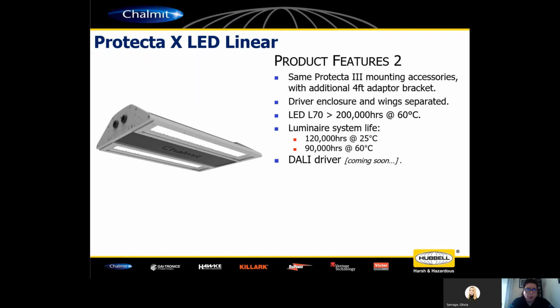I'm sure you're all aware that LEDs and electronics on the whole do not like high temperatures. They also don't like extreme low temperatures, so there's definitely a balancing act required there. Essentially, the point to take away is that at a sustained ambient of 60 degrees, the Protecta X luminaire will still achieve round about 10 years before you need any component replacement.